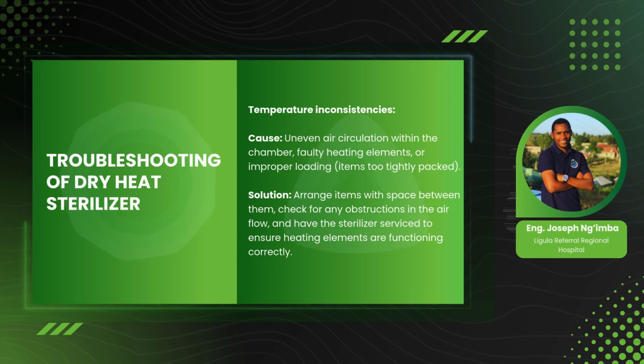Let's move to another part, the troubleshooting of these dry heat sterilizers. As we know, as long as we use this machine, it encounters some errors and problems because of different factors. For example, the effect of users, maybe they misuse the machine, or the system, maybe electrical faults, or the machine itself. So they generate some errors and problems that we need to solve. Let's check on the kinds of problems that may arise on these machines. The first thing to discuss is temperature inconsistency.